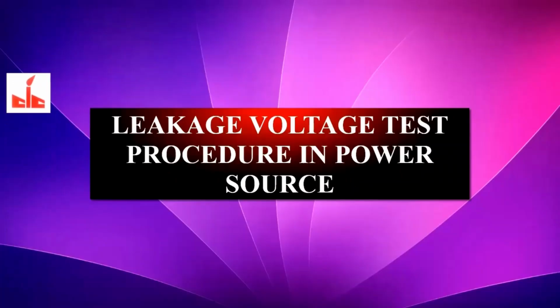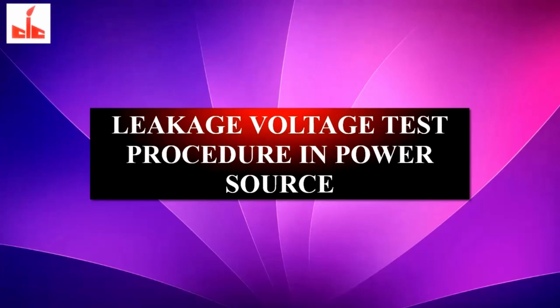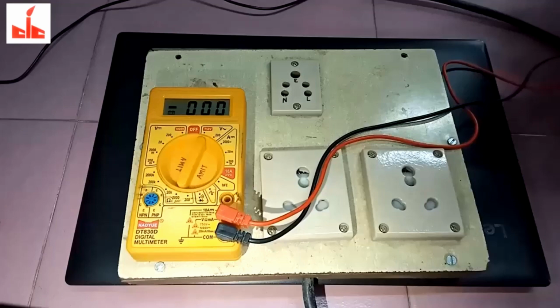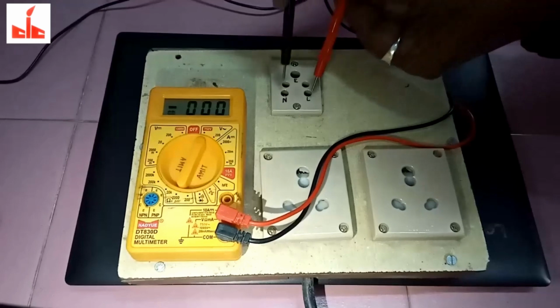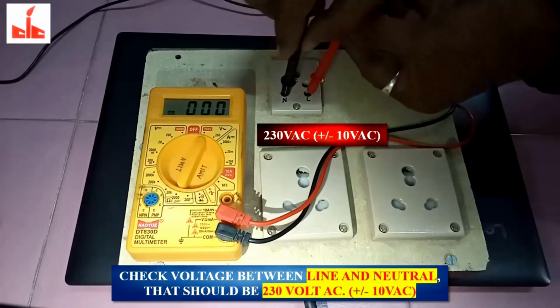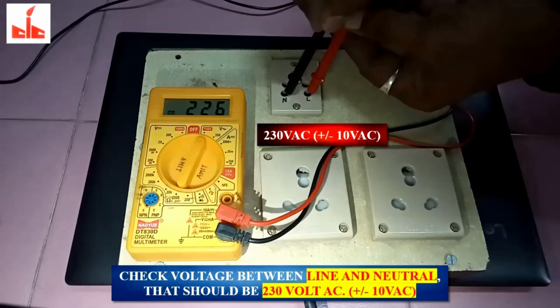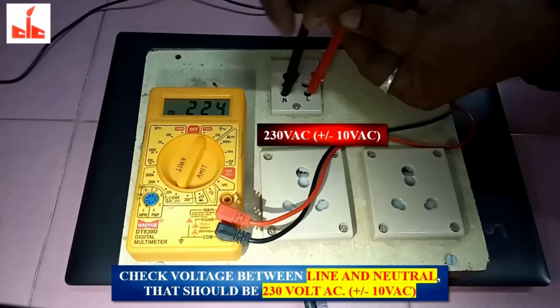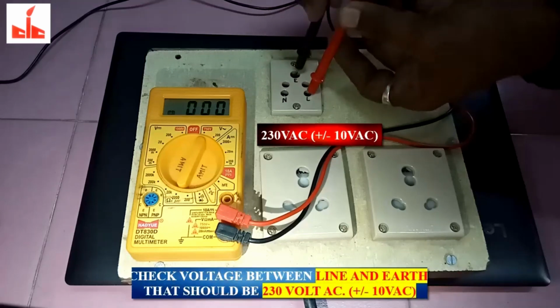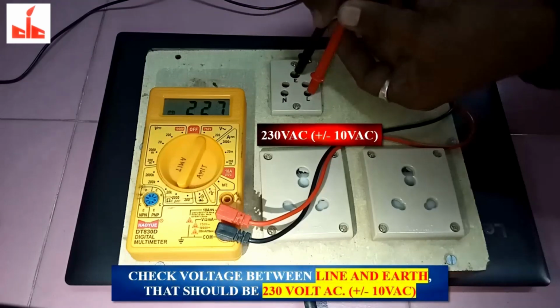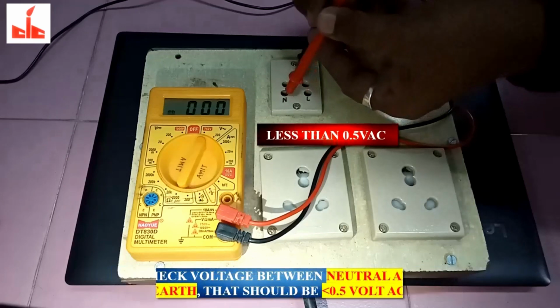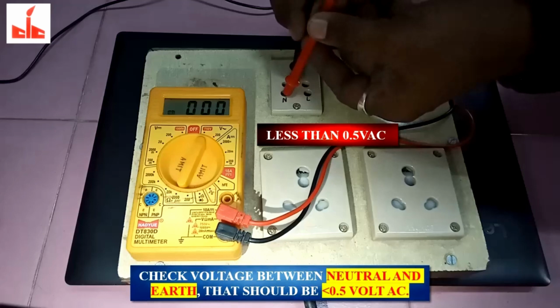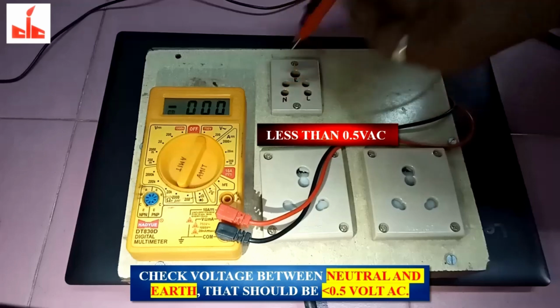Leakage voltage test procedure in power source. Before starting unboxing and installation, you must verify leakage voltage in the power source as per procedure. First, check voltage between line and neutral, that should be 230 volt AC, plus or minus 10 volt. Check voltage between line and earth, that also should be 230 volt AC, plus or minus 10 volt. Check voltage between neutral and earth, that should be less than 0.5 volt AC. If the power source is not correct, don't go for unboxing and installation.